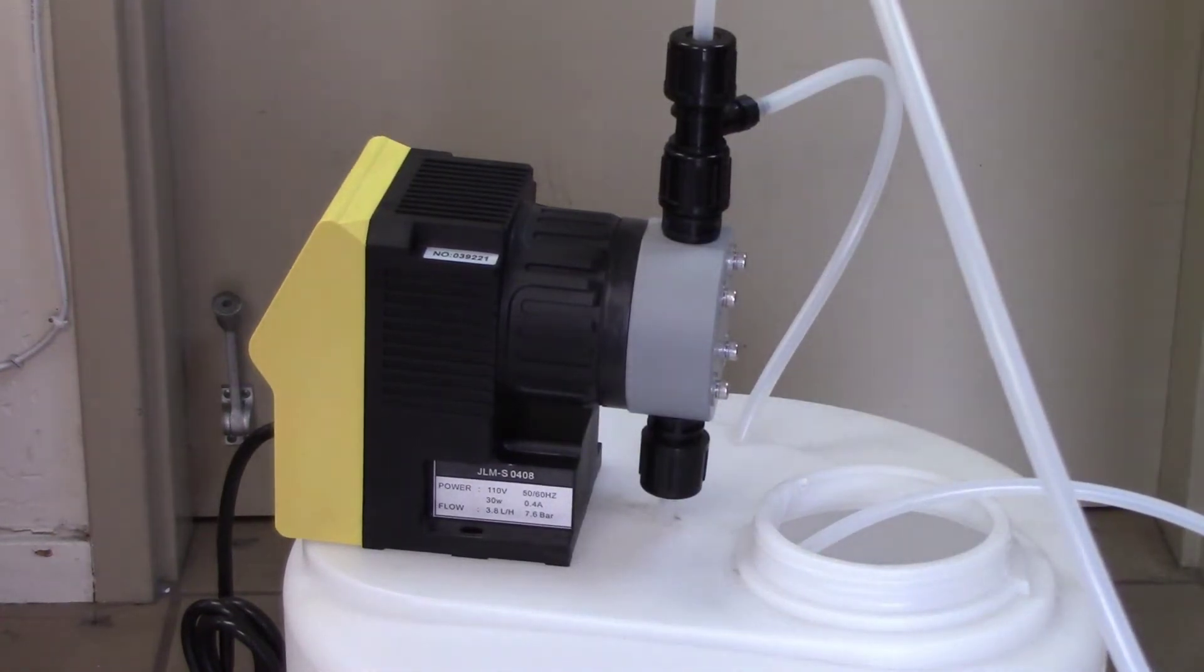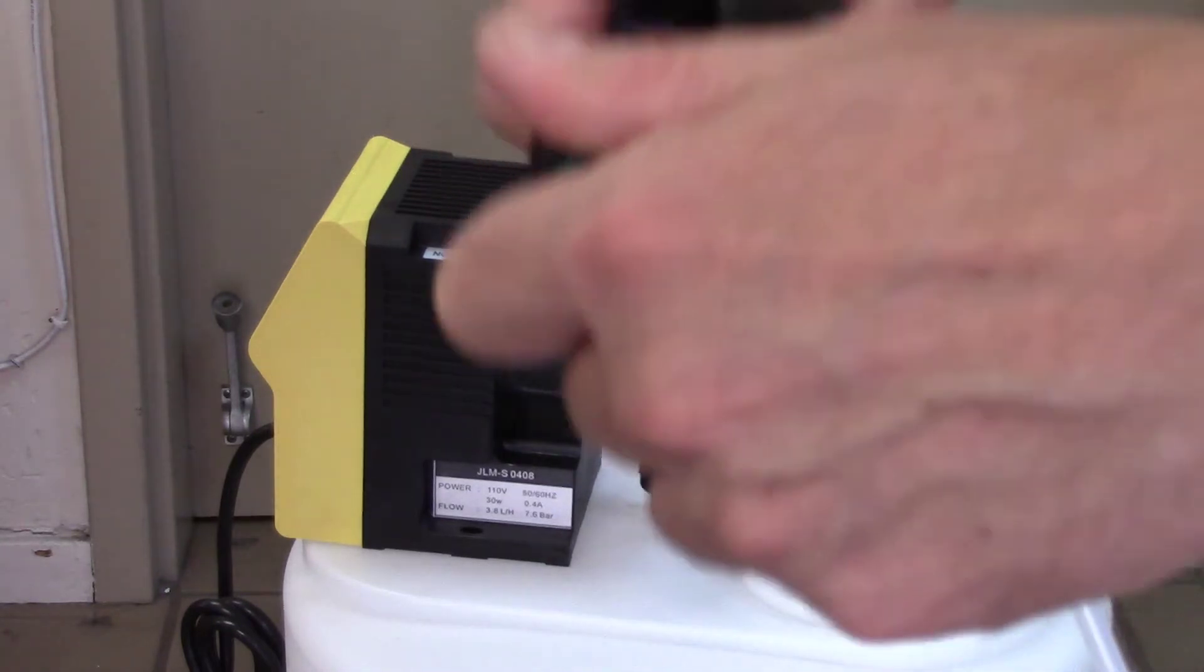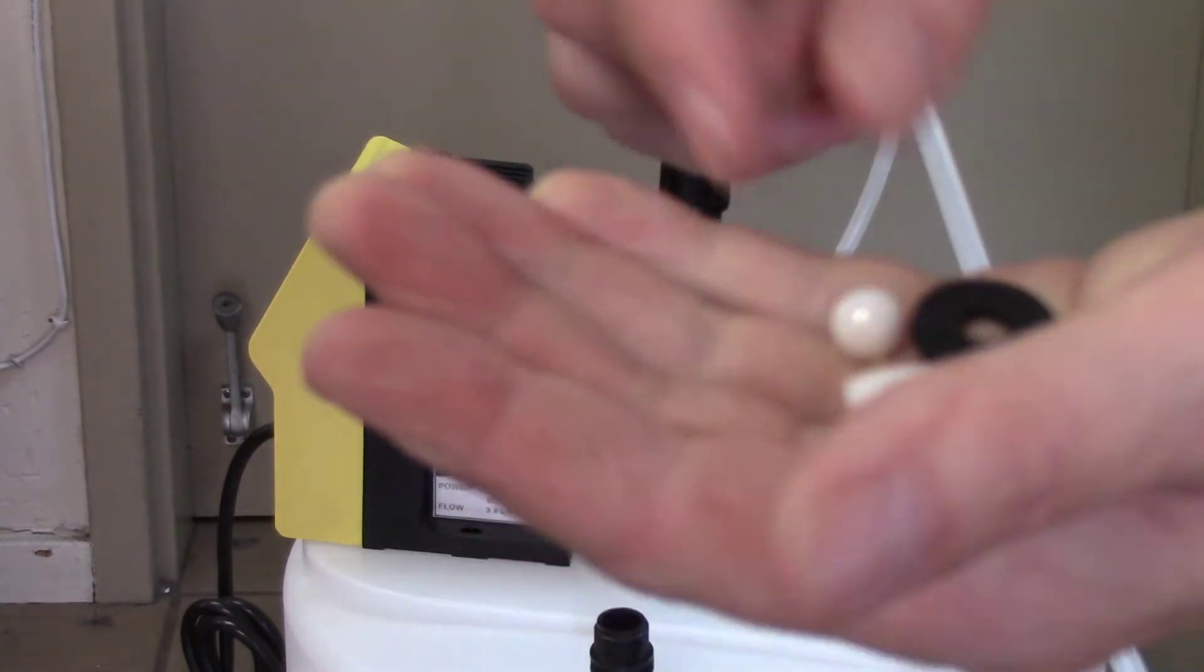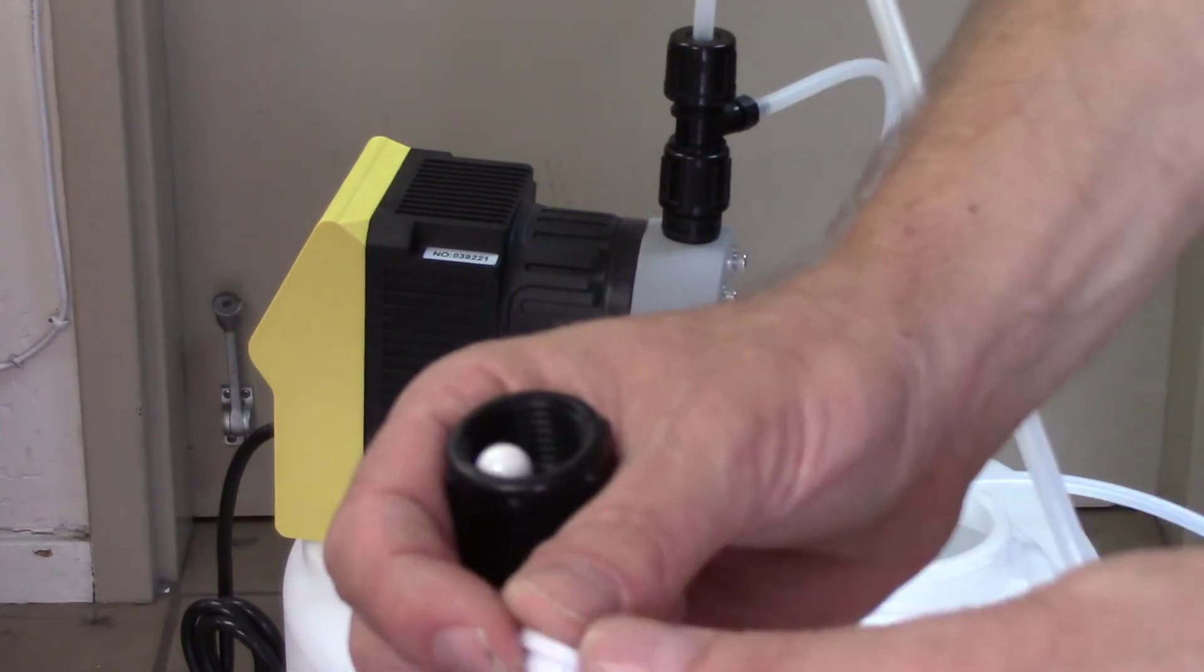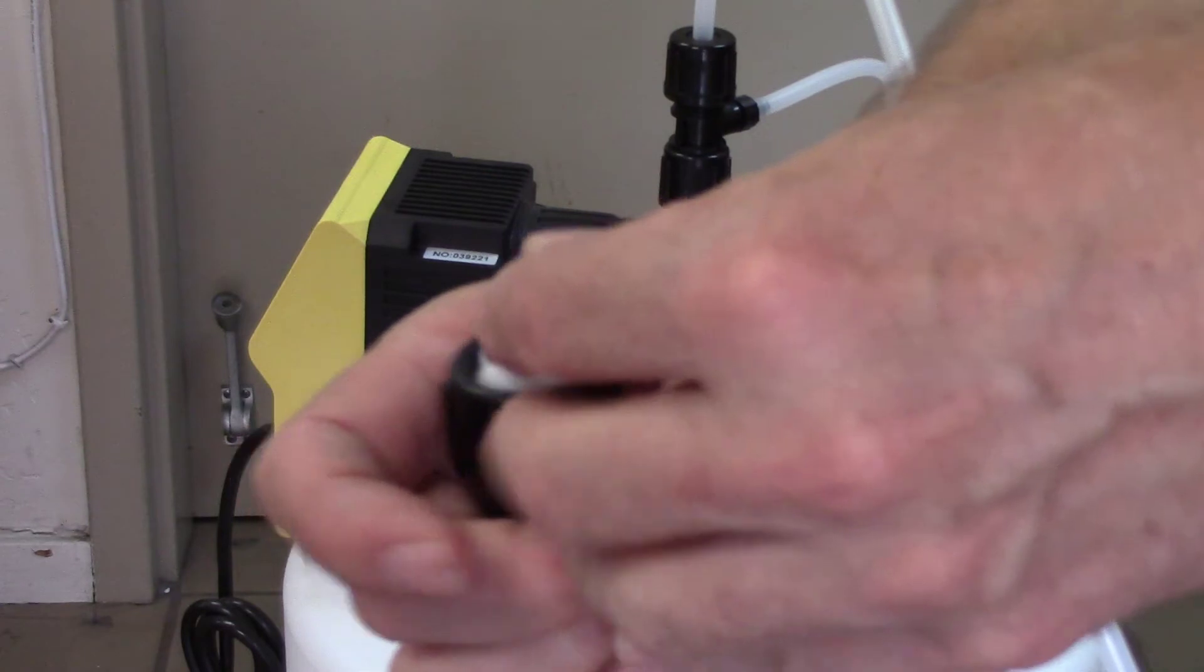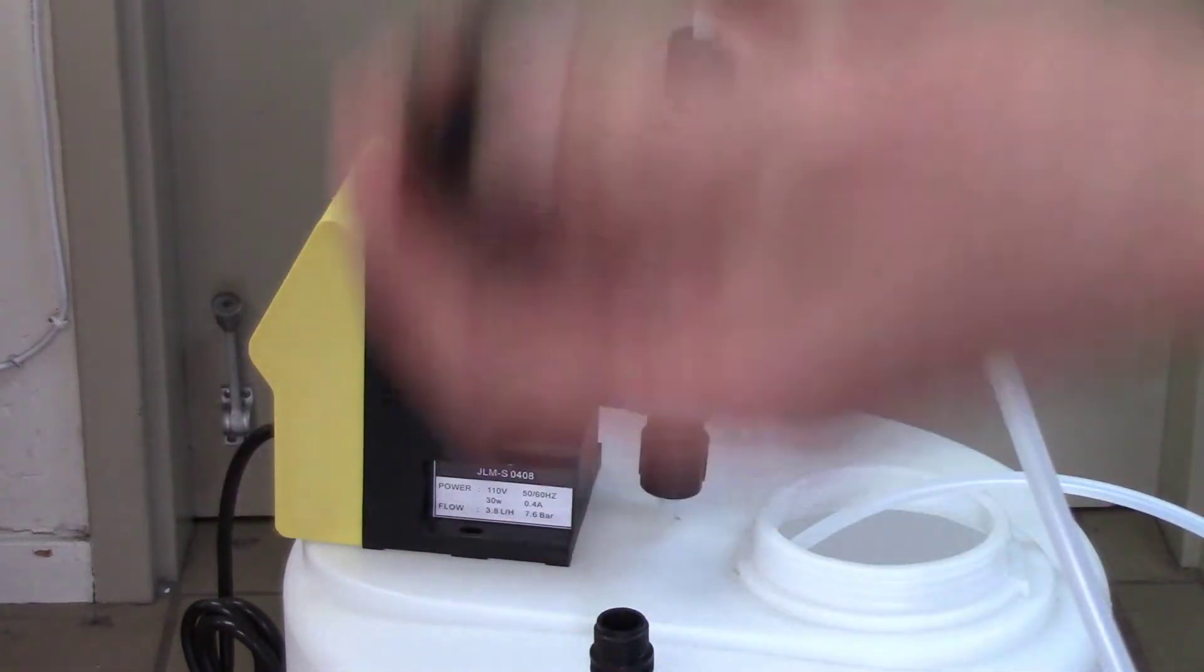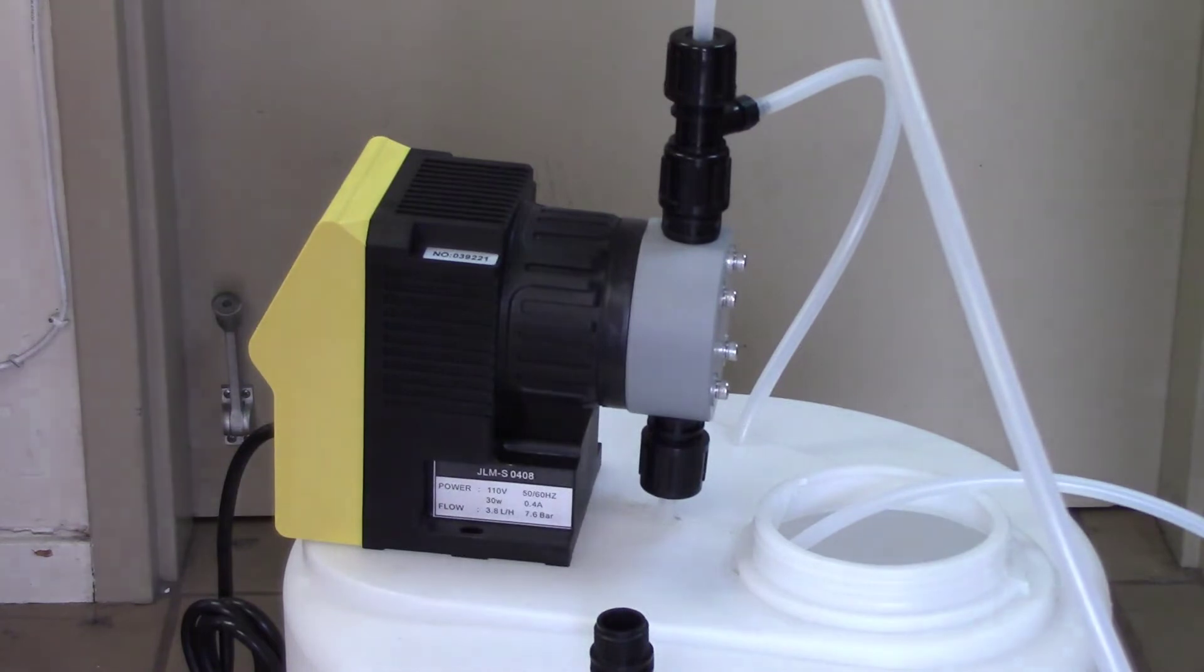One of them is this type, which is what the video refers to. On the inside of the injection check valve, when we unscrew it, we have the spring that holds the ball. There's a spring in there that holds the ball, and then there's the thing that holds the ball and spring down, and then there's the rubber washer that keeps it all as a tight seal and pushes it in. So you need to take all that apart and clean it and inspect it. If the spring is completely wore out, it is time to get a new check valve.